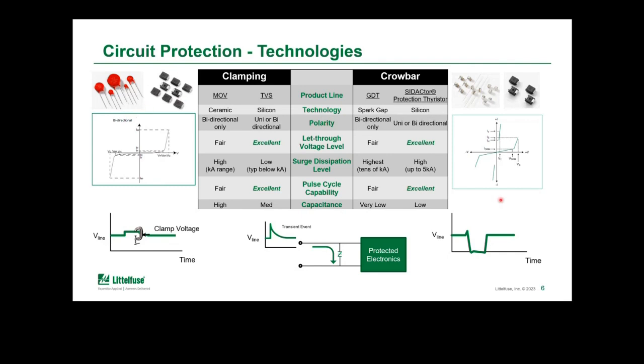The other type of technology is a crowbarring device. And how a crowbarring device works is once you reach a certain switch voltage, the voltage will actually drop to a near zero or very low voltage level that is some level below the operating voltage of the system. And then once the transient dissipates, it will delatch and go back to normal operation. And here's an example of a VI curve. This is actually for a sidactor. So you can see once you reach a certain voltage level, the voltage snaps back and we have a very low voltage level over a change in current.